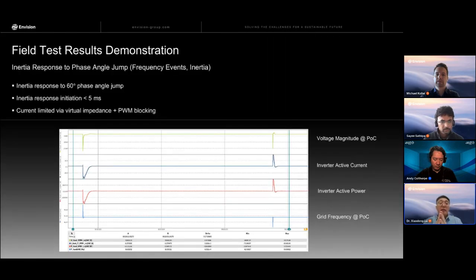The third one is about the phase angle jump. We did the test on site for the inertial response to phase angle jump up to 60 degrees, and we verified the response initiation time. It also helps us verify the current limitation, because the phase angle jump is the most challenging for current limitation. So we can see the effect of the virtual impedance current limitation. We can also see the PWM blocking when the current is limited by the software.